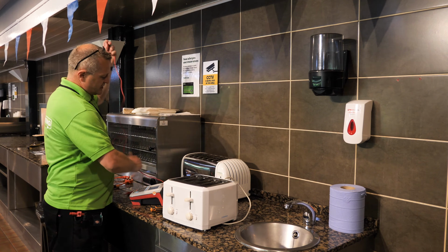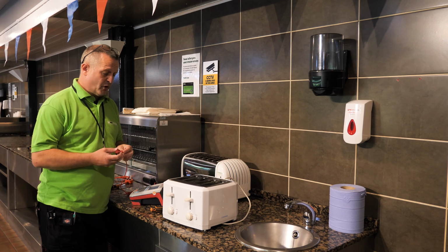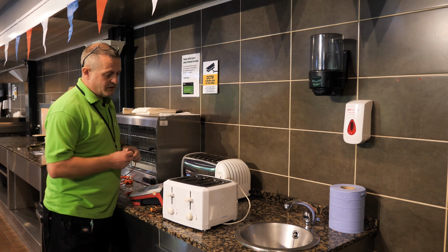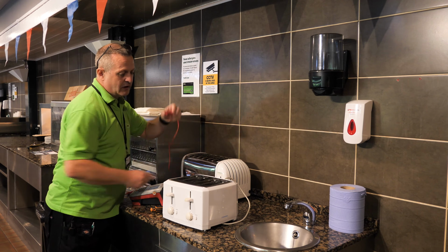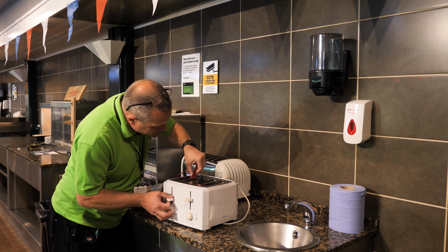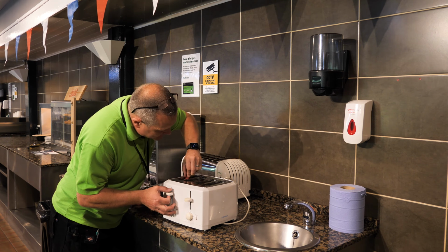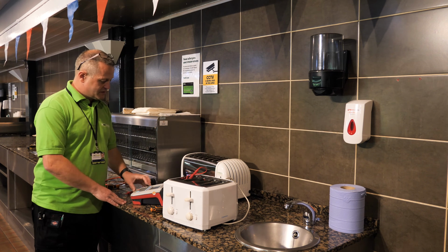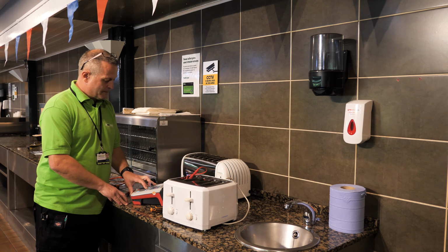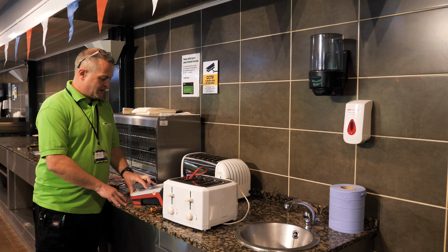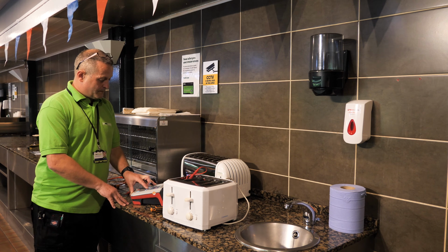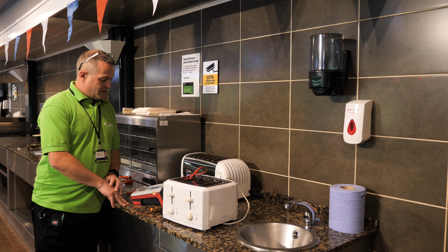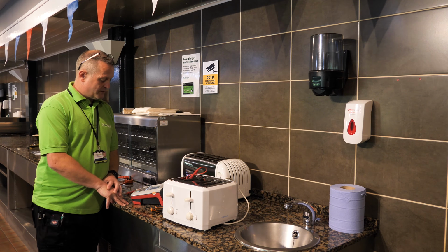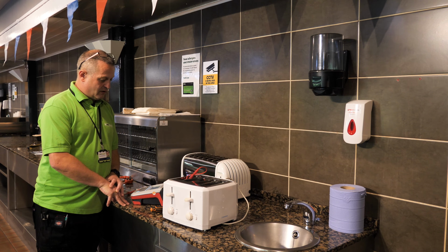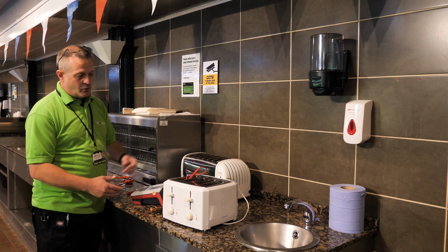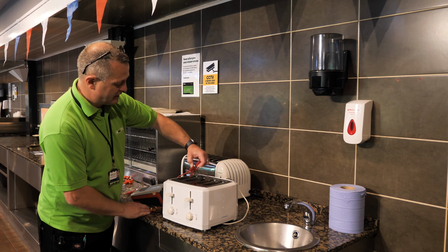And instead of using a probe on this occasion, I'm actually going to use a crocodile clip, but the probe will work perfectly fine. Again, just my experience is it tends to work better with the clip. And then we're going to get it onto the elements. And it's a class 1 test, so I'm going to select class 1 appliance test and let the machine do its thing. Showing 0.08 on the earth, and well over 20 on the insulation test, which shows that the appliance is working perfectly fine.